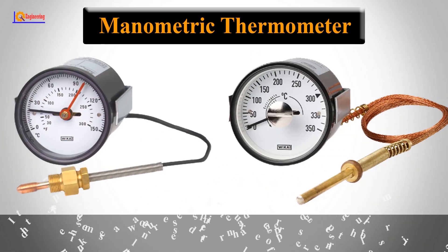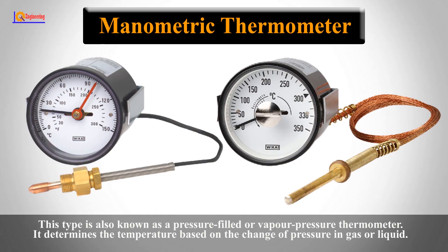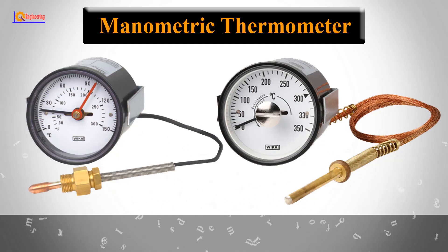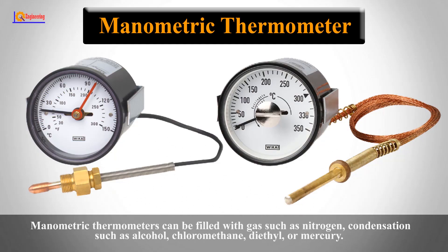Manometric thermometer. This type is also known as a pressure-filled or vapor pressure thermometer. It determines the temperature based on the change of pressure in gas or liquid. Manometric thermometers can be filled with gas such as nitrogen, condensation such as alcohol, chloromethane, or mercury.